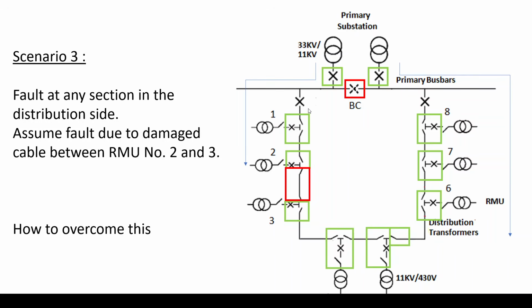So one possible solution for this is that, since my network was earlier opened in a certain part of the ring, now I have to feed this section which the power was not reaching. Now it had stopped here. I have to bring power for it from the other side of the ring, from here. So the power was available from here. What I would do is close this part of the RMU and power would flow from here all the way to reach the RMU here, which didn't have power due to this faulty cable. So I have now ensured that power can reach the remaining part of my ring from the other side, or from the other feeder.